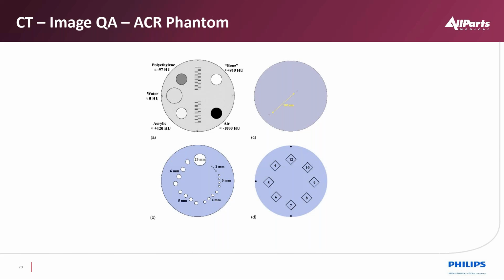Overseas in Europe, they use the Catphan phantom for the same purpose. It has some of the same elements, but as you can see, there are other things we check with regards to CT. Polyethylene has a -97 Hounsfield unit or CT number, water is 0, or simulated water as it's called. Acrylic would be a +120. If you take those ranges, you're dealing with most of the soft tissue in the human body. So this phantom is representing what we would see. On the extremes, we have the bone that's a +910.